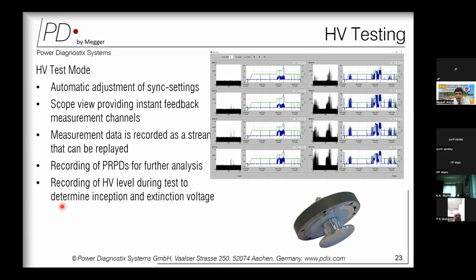But most important, this HV test is recorded for the trending and PRPD, and this can be used during future events to compare what was the reading or what was the behavior during HV test. And it is very important, where you can compare the behavior pattern of new GIS and the old age GIS.